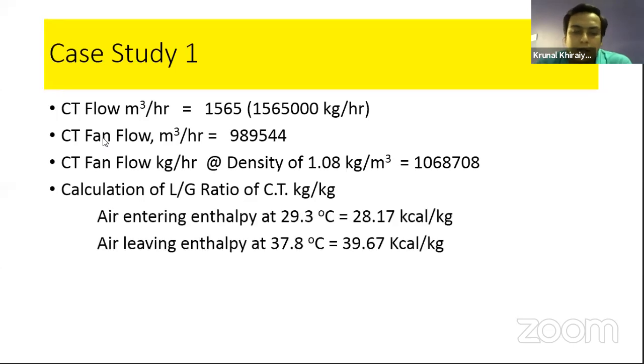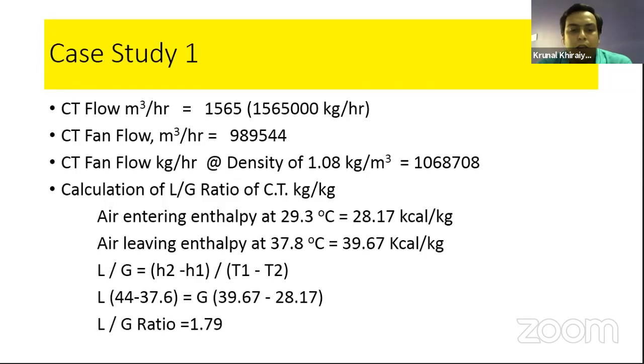Now, important parameters, yes, I definitely say that the L to G ratio of the cooling tower is a very important parameter. Here, using the sling psychrometer, we measure the wet bulb temperatures of air entering and air leaving, and from that we find the enthalpy using the psychrometric chart. So we get 28.17 kilocalorie per kg and 39.6. See here, the kilocalorie. I said that if you are using a unit of kilojoule per kg Kelvin for the Cp, and if the enthalpy unit is kilojoule per kg, then you have to divide by 4.186. So, revising the formula: H2 minus H1 divided by T1 minus T2. From that the L to G ratio, an important parameter, is 1.79.